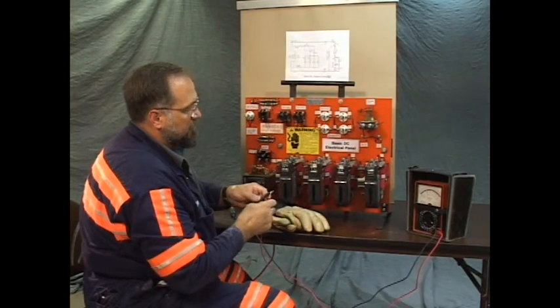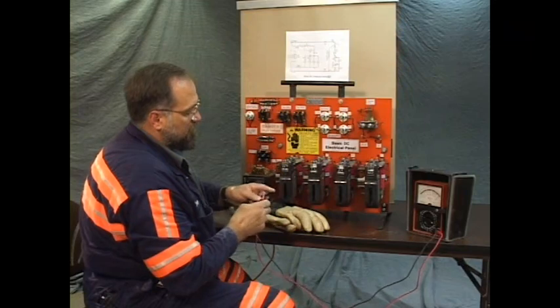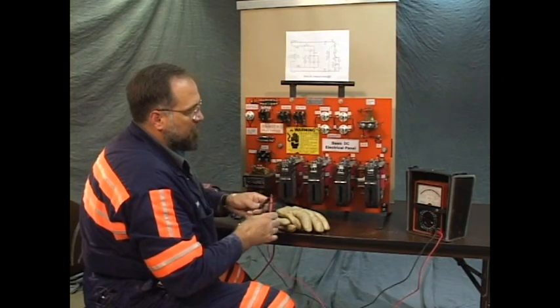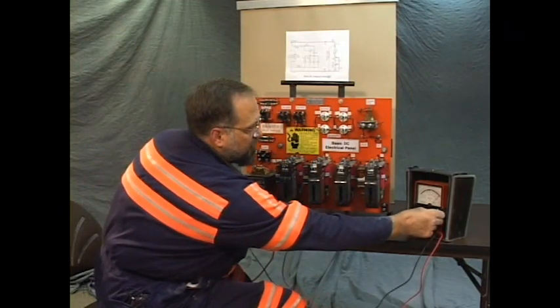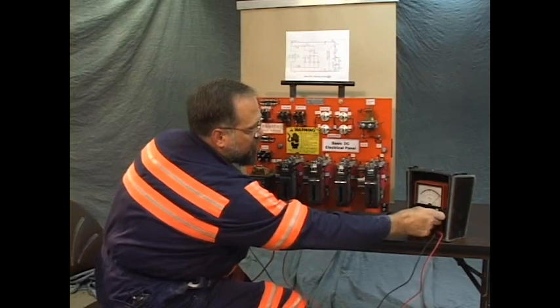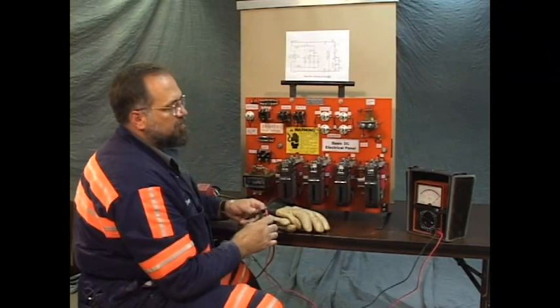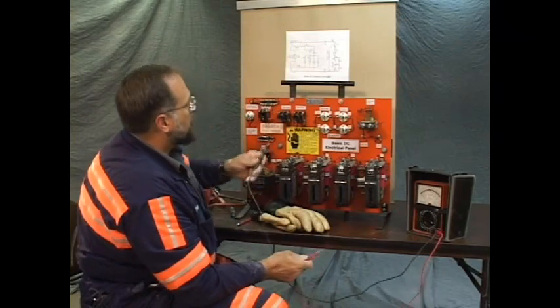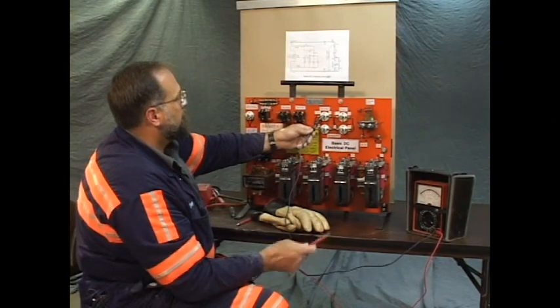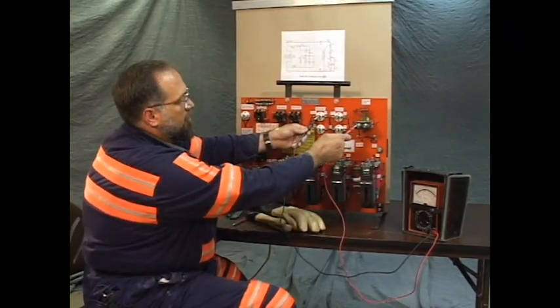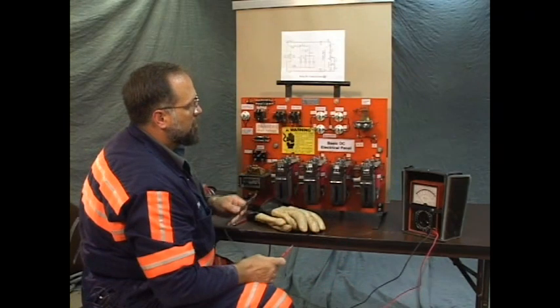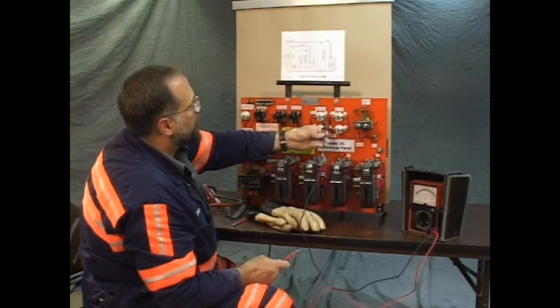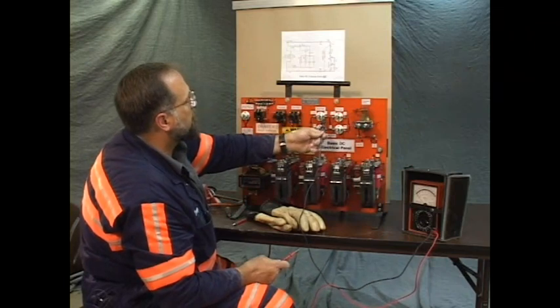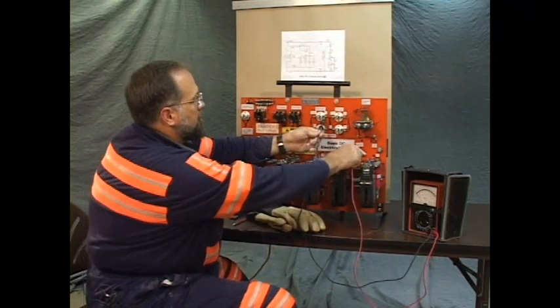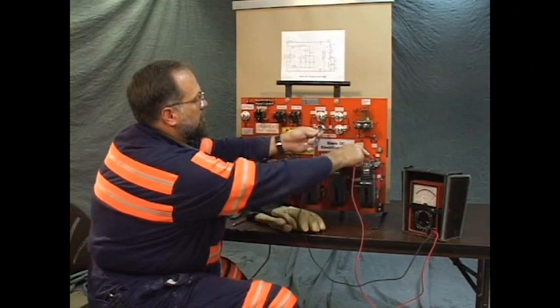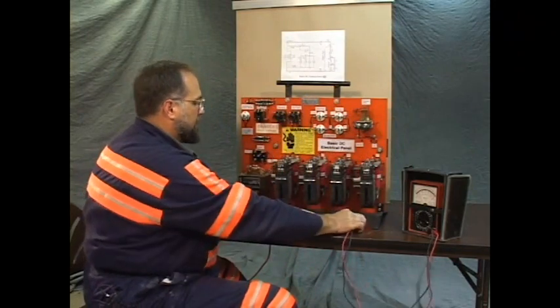Let's test our meter. We zeroed this meter earlier, but sometimes they need a little touching up. Like now, we're going to touch this one up to re-zero it. And we're confident our meter is operating correctly. Check from here to here. No circuit. Well, just for curiosity's sake, let's check the other side of that circuit. From there to here. So, it shows intact.